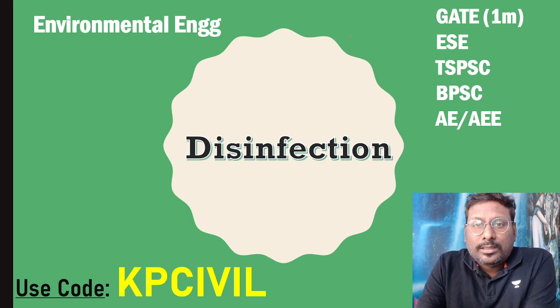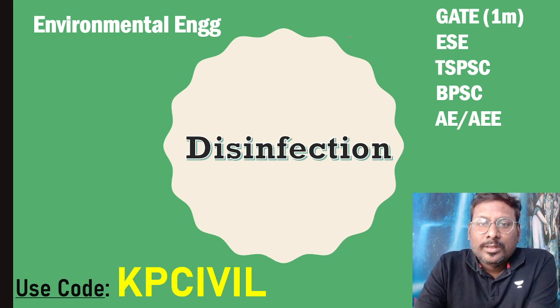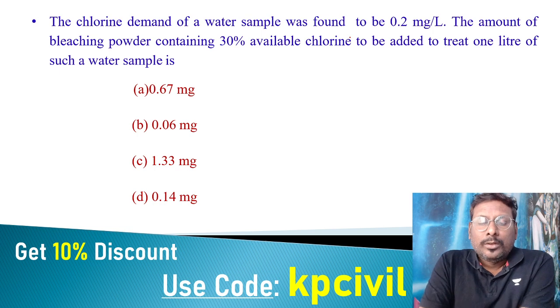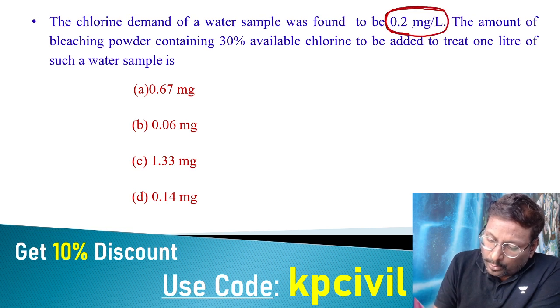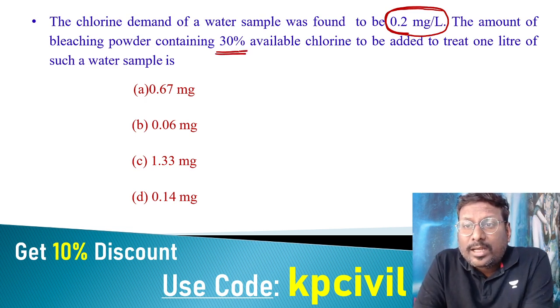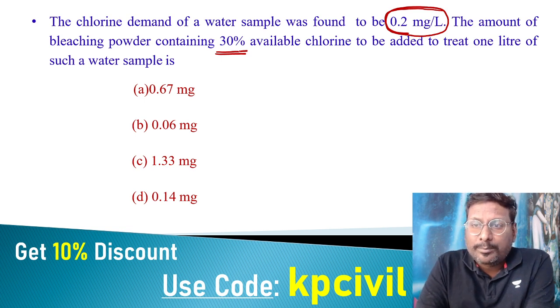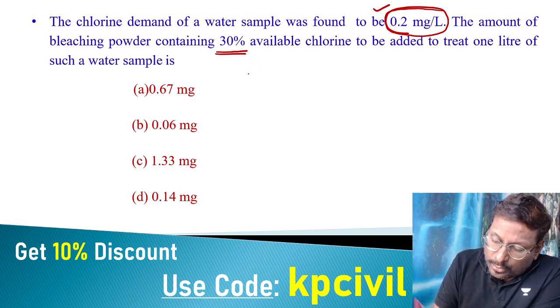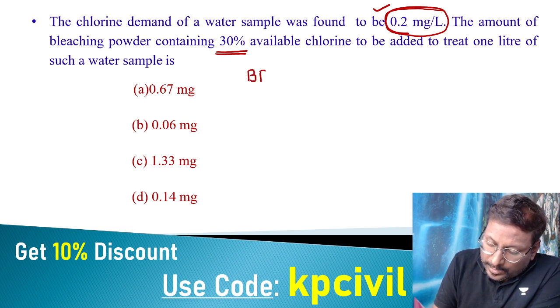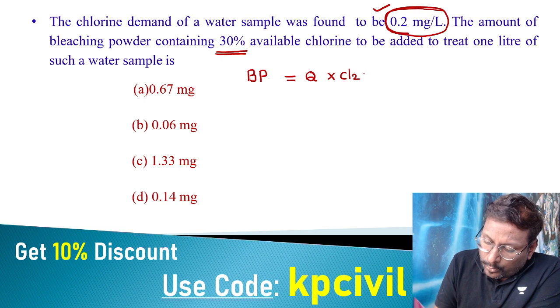We have completed few topics like sedimentation, coagulation, and filtration. Now we cover disinfection — the last method of water treatment after filtration. The chlorine demand of a water sample was found to be 0.2 mg/L. We need to find the amount of bleaching powder containing 30% available chlorine to be added to one liter of water sample. Since no residual chlorine information is given, take demand as dosage. The formula is: Bleaching powder quantity = (Discharge × Chlorine dosage × 100) / Percentage of chlorine.